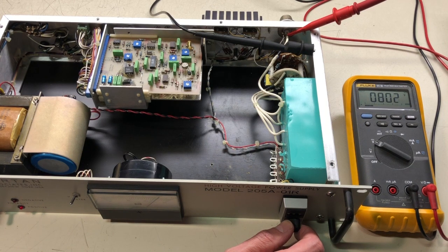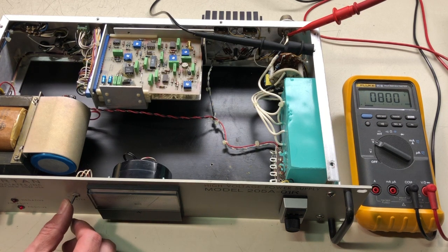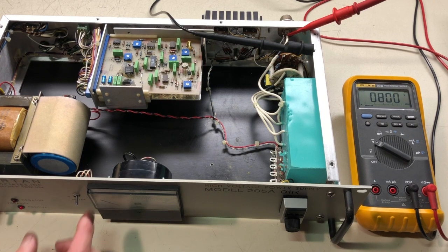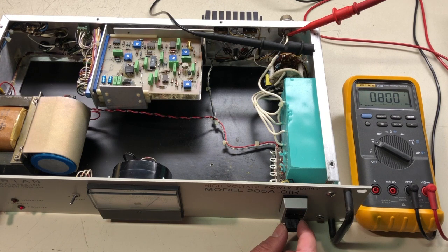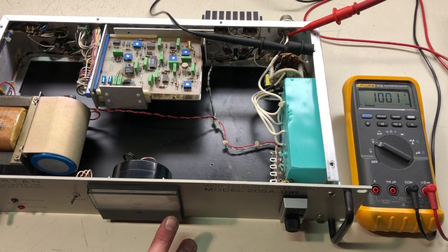All the way to 800. Yep, got 800 volts. That looks good. Flip this over here to current. Yep, still down at 0, so that's good. And there we have it. There's the 1,000 volts. There it is. Very cool. So it's able to generate the 1,000 volts. That's the full rated output. And the meter is right on 1,000 full scale deflection all the way over.